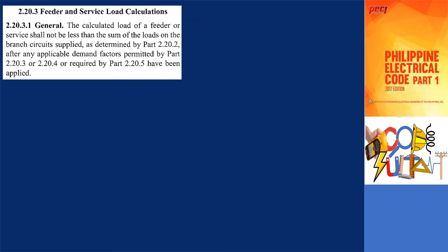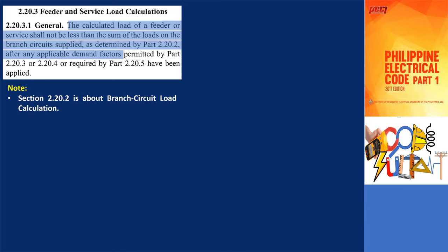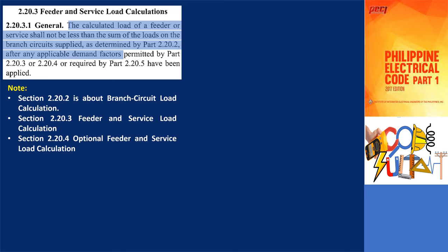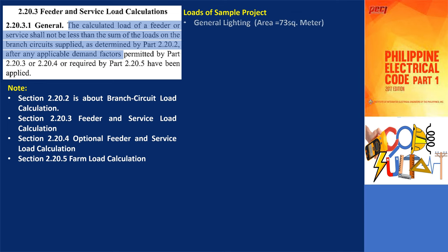The rules of the code for feeder and service load calculation state that the load shall not be less than the sum of the loads on the branch circuits after applying the demand factors permitted in this section, or by the optional feeder and service calculation method, or as required by the farm service calculation. To understand this section, let's apply this to our sample project.